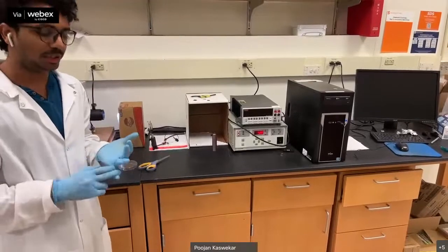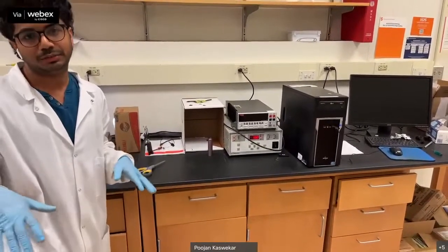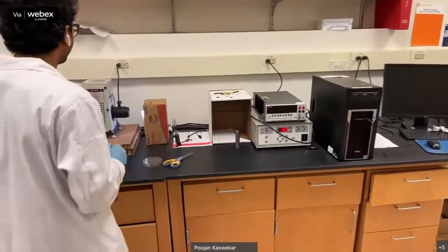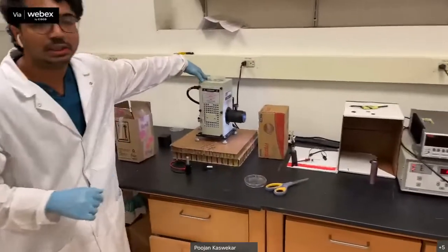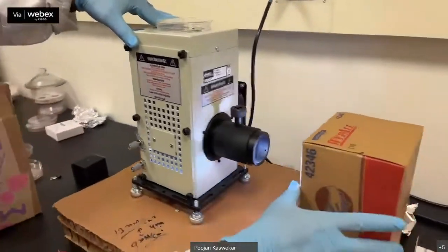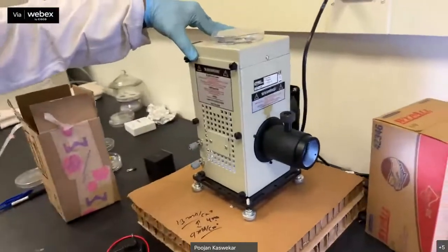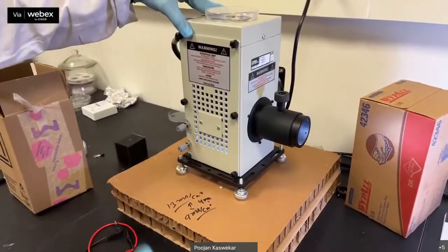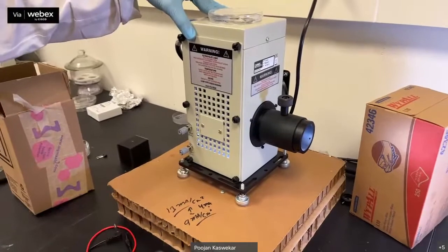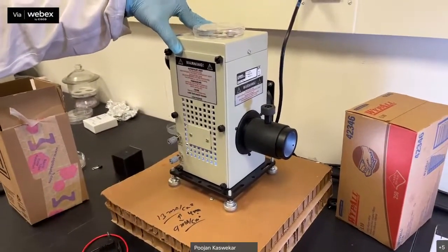You can measure anything. You can measure silicon. You can measure perovskite. If you know the area of your sample, that should be good enough. So there is the xenon arc lamp housing. There will be a xenon arc lamp. I already turned it on. Normally, you want to turn it on at least 15 to 20 minutes before your experimentation, because the lamp needs to be heated up to give you a stable illumination.